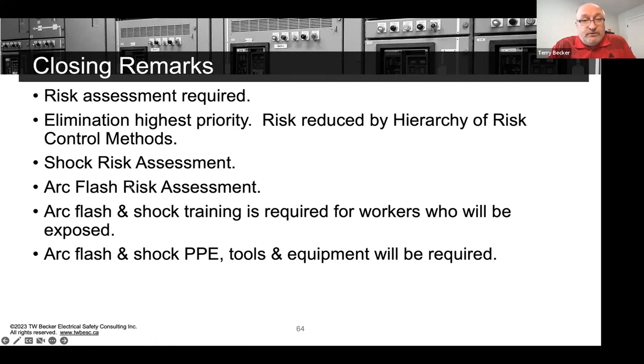The two tools for the worker. These are tools for the worker. The worker completes the shock risk assessment. The worker completes the arc flash risk assessment, and they document it. We need them to take more ownership. We need them to take control for any workplace hazard. You help them, give them the tools, then they apply it in the field. So we want them to own identification of these hazards, apply the boundaries, select the PPE, and use other hierarchy of risk control methods that you provided them to minimize their risk, reduce it to as low as reasonably practical.